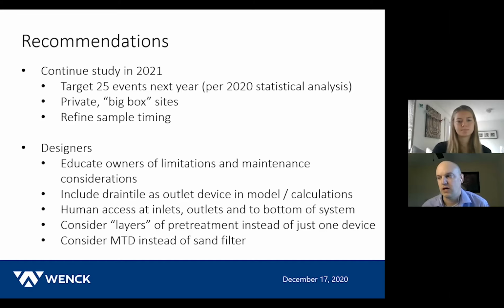Some recommendations for designers: continue to educate your owners and clients as to the limitations and the maintenance considerations. Ultimately, at some point, these systems are going to need the filtration capacity of that sand layer restored. Our oldest system is 8 years old, and it doesn't look like that particular system has failed. So maybe it's going to fail in 10, 15, 20 years. But are owners ready for that sort of investment? A couple hundred thousand dollars to rebuild this sort of system.